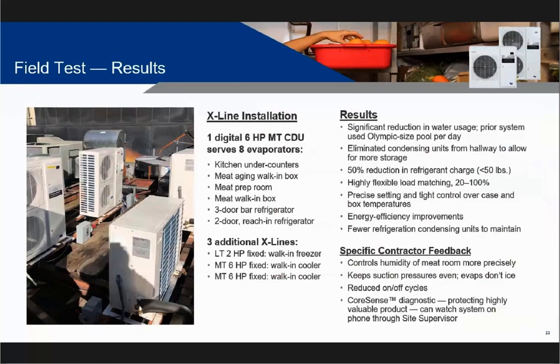Looking at the results, there's a significant reduction in water usage. They had hired a consultant to evaluate how much water they were using, and it was close to an Olympic-sized pool per day, a massive amount in New York City, which was clearly not cheap. They eliminated the condensing units from the hallway, and because they consolidated so many units and line runs, they reduced the refrigerant charge by 50%, ending up at less than 50 pounds for the entire restaurant. There's highly flexible load matching, precise setting and tight control, energy efficiencies, and fewer units to maintain going forward.